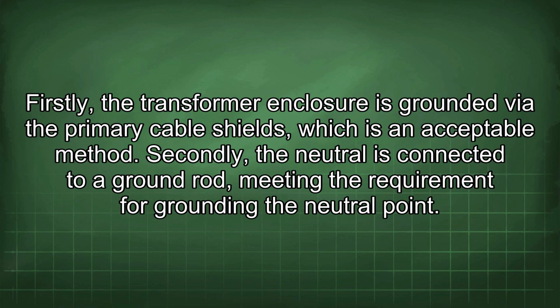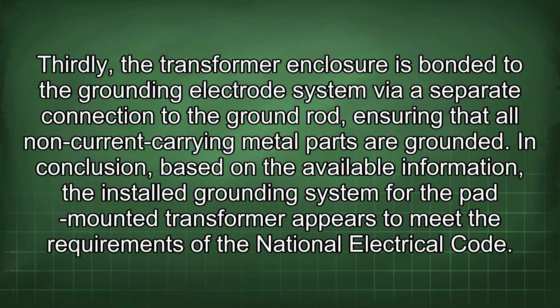Firstly, the transformer enclosure is grounded via the primary cable shields, which is an acceptable method. Secondly, the neutral is connected to a ground rod, meeting the requirement for grounding the neutral point. Thirdly, the transformer enclosure is bonded to the grounding electrode system via a separate connection to the ground rod, ensuring that all non-current carrying metal parts are grounded. In conclusion, based on the available information, the installed grounding system for the pad-mounted transformer appears to meet the requirements of the National Electrical Code.